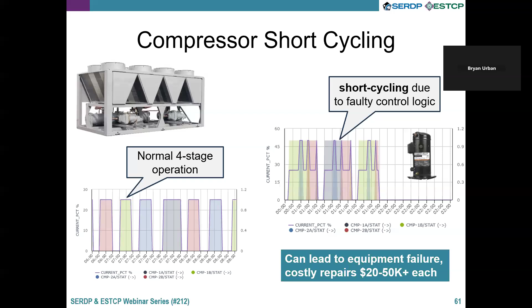In this case, we were not able to fix the problem because it wasn't part of the facilities control system. It was part of the logic that was built into the chiller unit, and that was controlling the compressors. So in those cases, you can work with the vendor directly, let them know next time they're on site to tweak the logic, or if you have warranty claims or otherwise, you can work to provide the data or the evidence that there's some problem with their system. So another example of a different kind of use case.